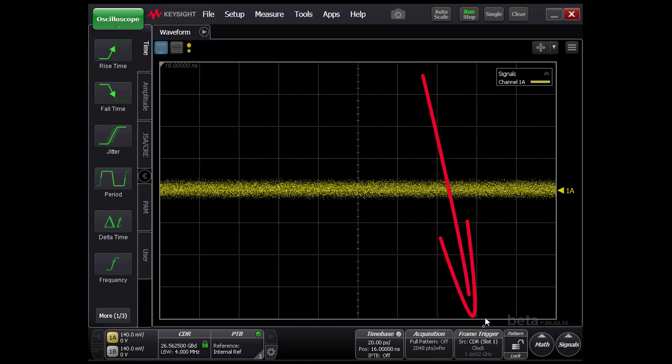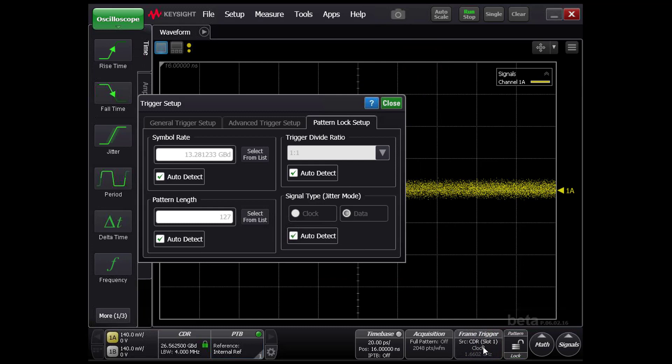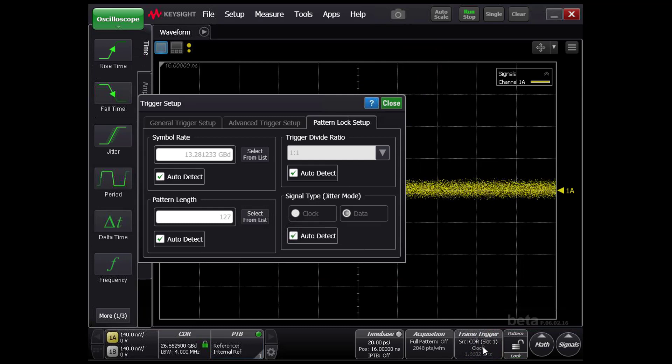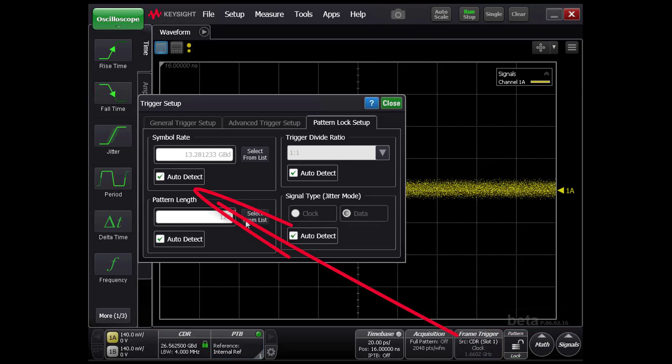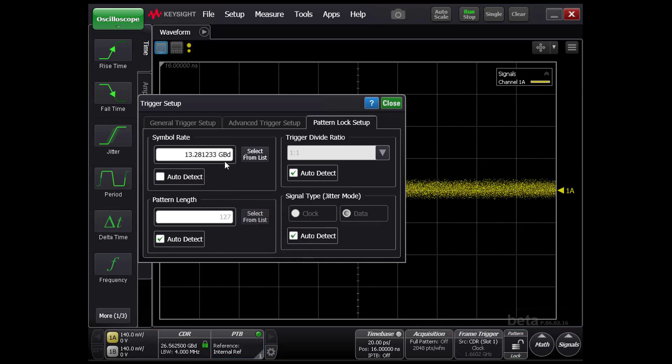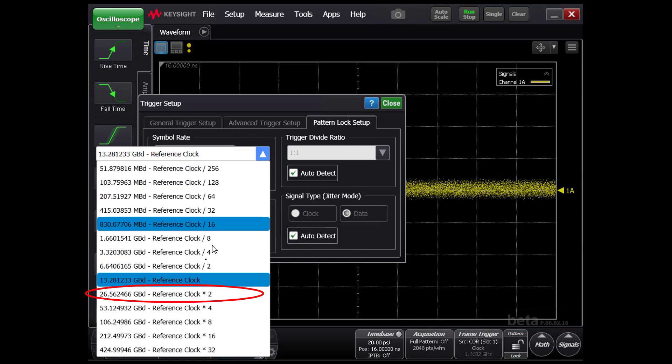Since the signal is severely degraded, we will manually set the symbol rate to 26.5625 gigabaud and attempt a pattern lock.